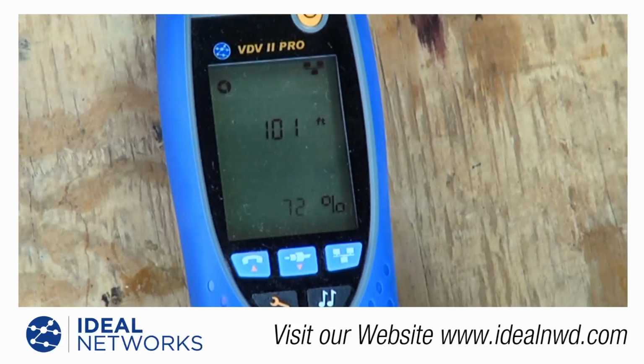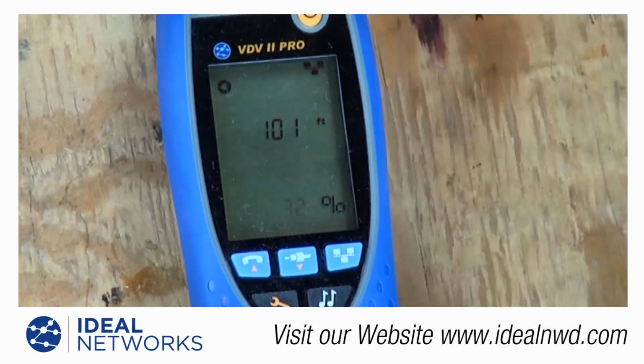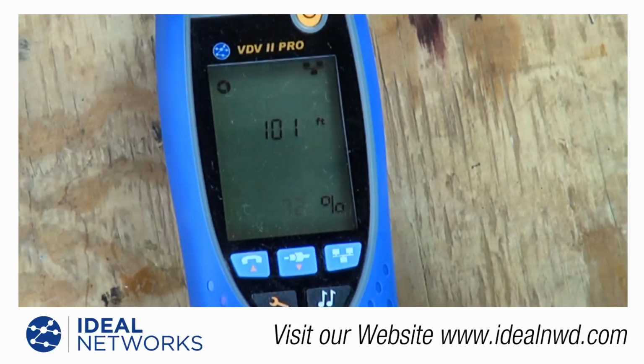Keep in mind that in category wires, the pairs are twisted, and cable is always marked on the outside by its length, say 100 feet. But internally, the cable is longer electrically than its physical length. In Category 5E, that's roughly 5 or 6% longer, so a 100-foot cable is really more like 105 or 106 feet. In Category 6, it's 10 to 12% longer, and in Cat 6A it can be even more. So again, knowing the NVP matters.